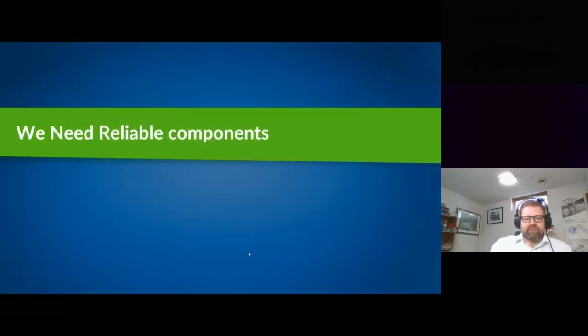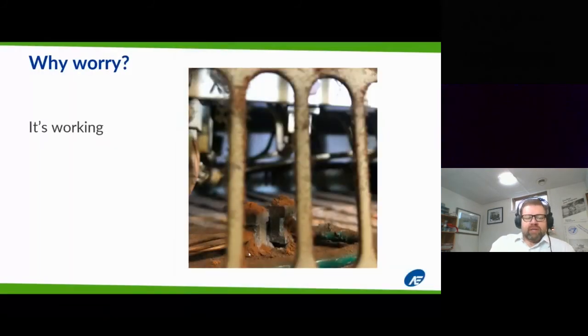So the takeaway message here is we need reliable components. You've got to maintain them, keep an eye on them, and make sure that they're working properly. This is a picture of a transformer that is only 20 years old. This is the ground lug at the bottom of the transformer. Notice the powdered rust collecting on top of the ground lug. This transformer is working, it's happy, it seems to be a little bit warm, but it's also piling up rust on a day-to-day basis because of the amount of corrosion.